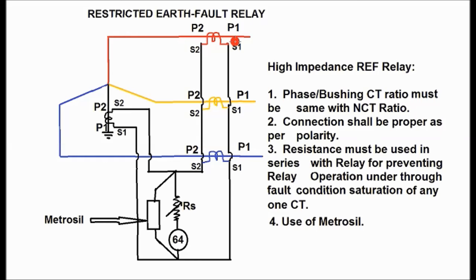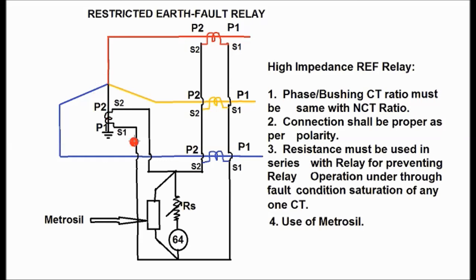P1 is connected towards the bus side and P2 is connected towards the transformer side for all the bushing CTs. If taken from the bushing CT, P2 shall be towards the transformer side for all the phases. For the neutral CT, P1 shall be connected towards the earth side and P2 shall be connected towards the neutral side.